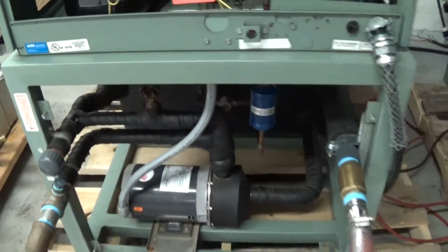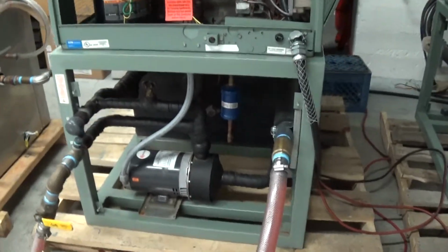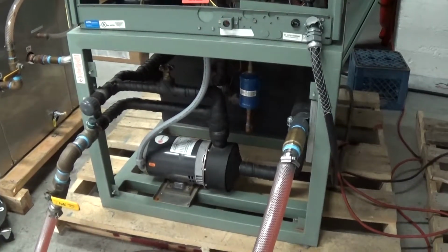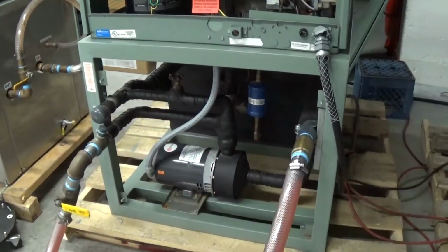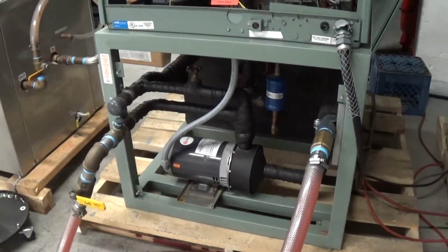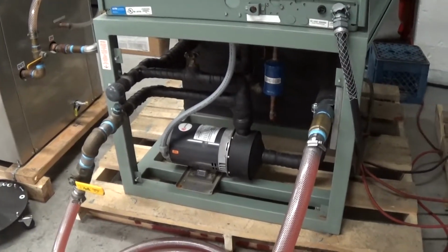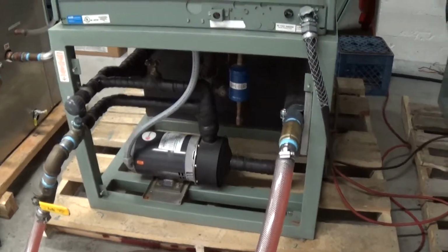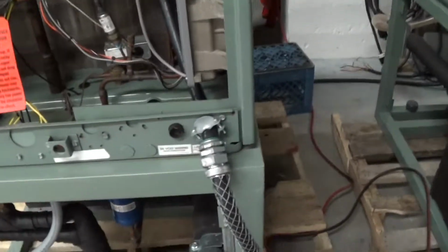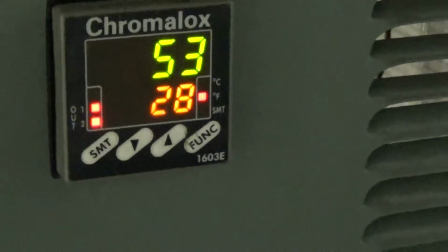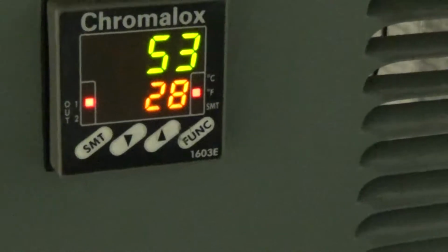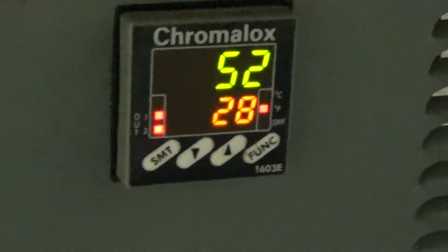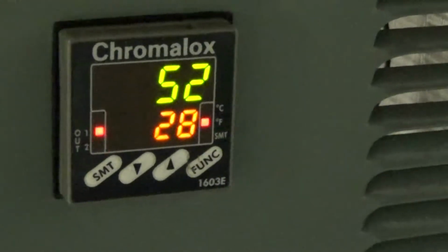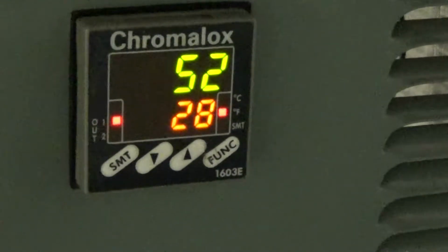The reason for that is a brazed plate heat exchanger requires a certain amount of pressure and flow to behave correctly. By piping it this way, we avoid the need to have high pressure in your return lines on your return side of your glycol brewery piping. This is an R410A refrigerant, by the way. You can see we're already down to about 53 Fahrenheit. This unit will probably go a couple degrees below set point before it stops, and it'll probably wait until you're a couple degrees above set point before it comes back on again.